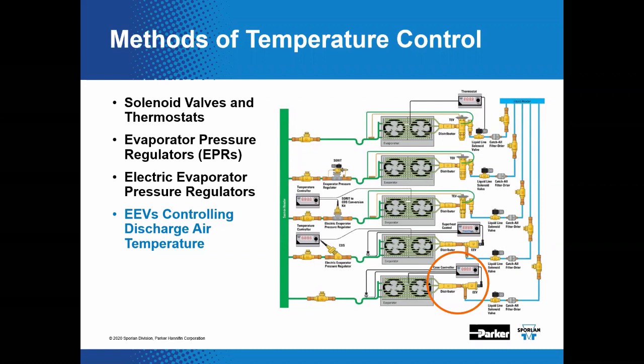Some controllers have the ability to control an EEV to not only a desired discharge air temperature, but they can also monitor the evaporator's superheat. Superheat is a safety to protect the compressor from liquid damage. Some common vapor compression refrigeration systems actually use this control method. We haven't dealt with the aspect of controlling pressure with this technique, and there is some concern that operating a case at common suction pressure will cause perhaps additional frost, odd frost patterns, maybe impact the humidity level in the case. I guess we'll see. We shall.